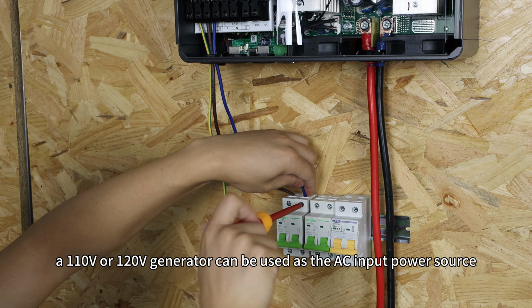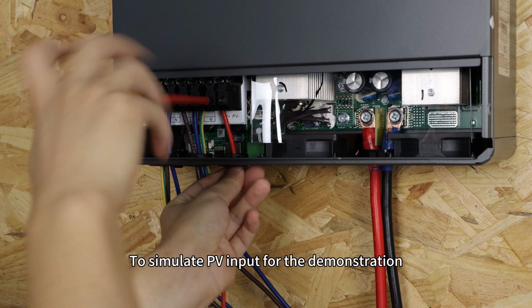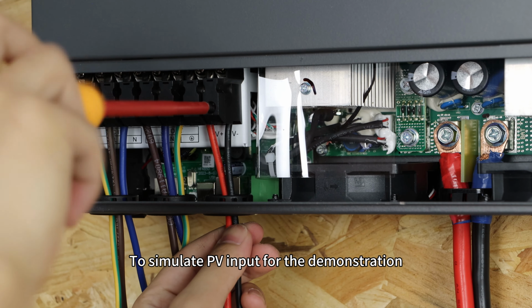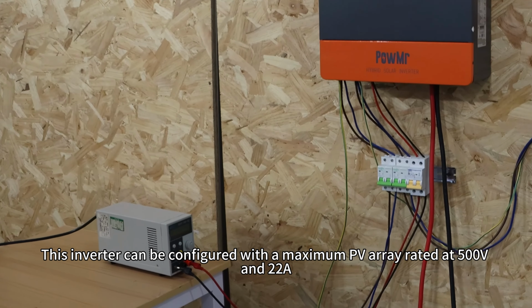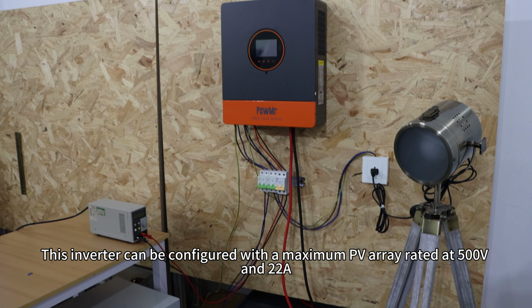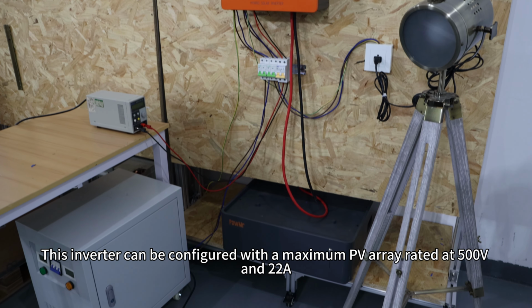For the AC output line, we've connected a power outlet to simulate typical household electrical loads. Similarly, a 63-amp AC circuit breaker is installed on the AC output line. To simulate PV input for the demonstration, we've used a programmable power supply, which will allow us to showcase the status of sufficient and insufficient solar power later on. This inverter can be configured with a maximum PV array rated at 500 volts and 22 amperes.